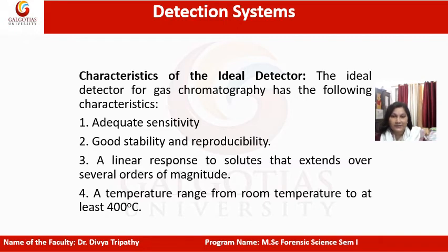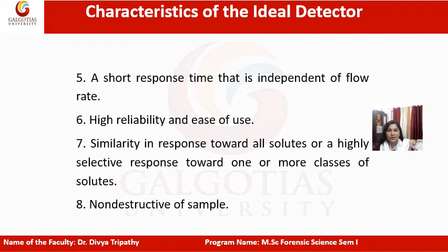First is adequate sensitivity, good stability and reproducibility, a linear response to solutes that extends over the several orders of magnitude, a temperature range from room temperature to at least 400 degrees centigrade, a short response time that is independent of the flow rate, high reliability and ease of use, similarity in the response towards all solutes or a highly selective response toward one or more classes of solutes, non-destructive of sample.